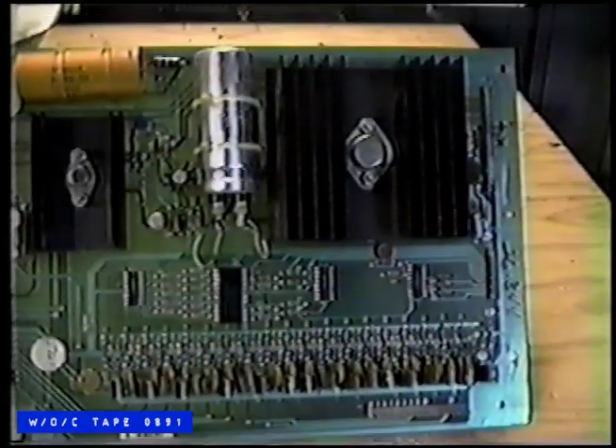Let's take a look at the schematics now. This is where we'll get most of our information for troubleshooting. I've circled the section we're interested in because we've lost 5 volts to the MPU. Usually when that LED doesn't light up or flicker or flash, you've lost logic power, which is the 5 volts. It originates down here in this section on the transformer, as shown on the schematic. You've got a bridge rectifier there taking about 12 or 13 volts off the transformer, rectifying it down to 11.9, which then heads directly from there into the voltage regulator.